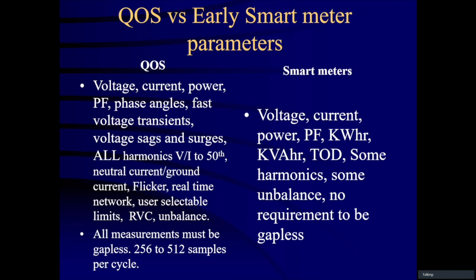Smart meters, so this is where we compare the quality of supply to the revenue smart meters. So voltage, current, power, power factor, KW hours, KVA hours, TOD, some of the harmonics, some unbalanced. The big difference is there's no requirement for it to be gapless. In other words, it can be sampled.